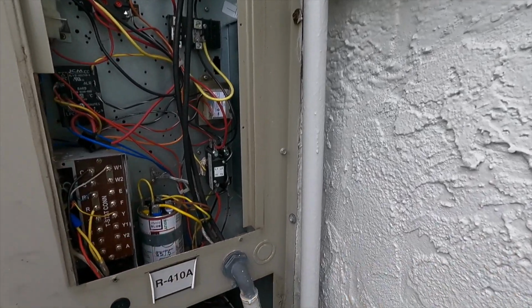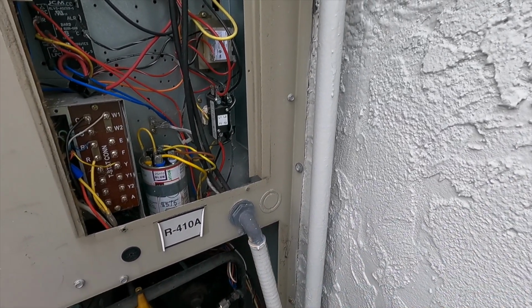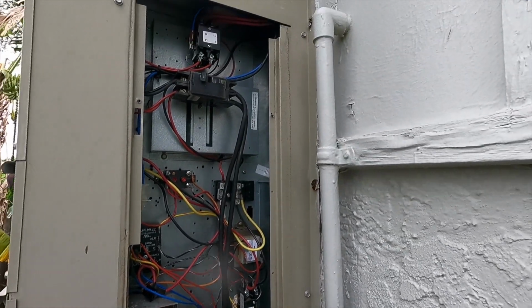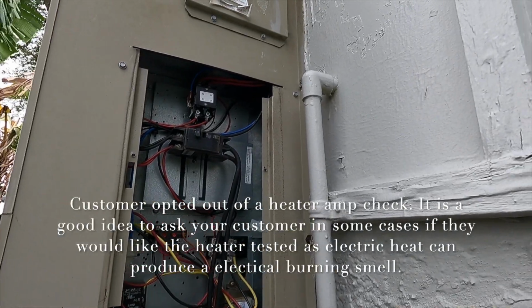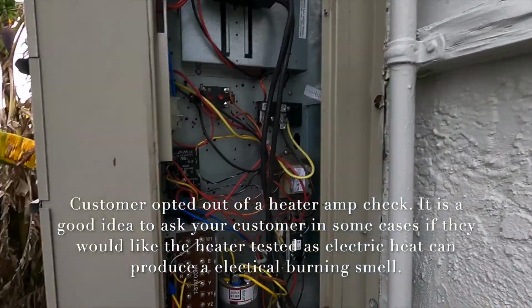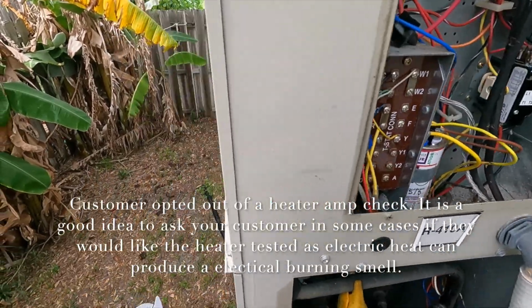Blower motor amp draw, a condenser fan amp draw, a compressor amp draw, and the only other amp draw we're looking for is the electric heat at this point. So we'll take that measurement here at the end.